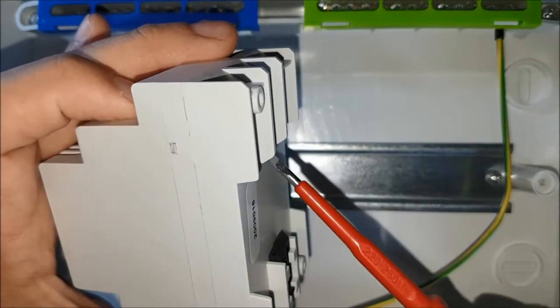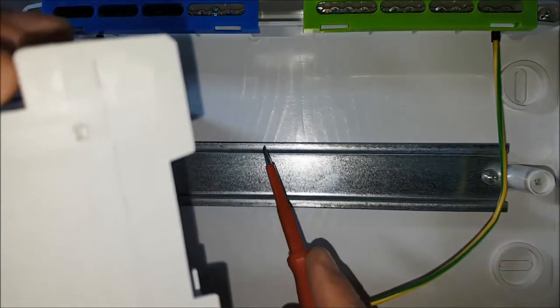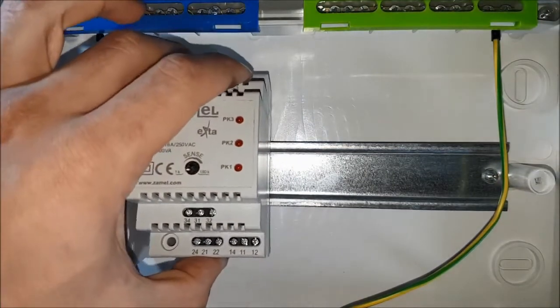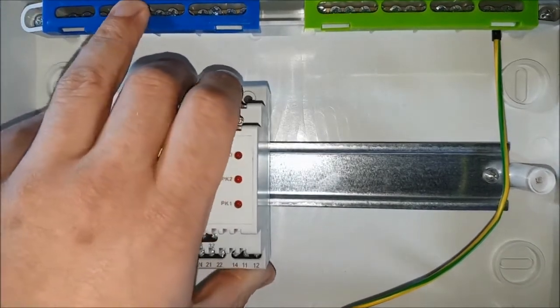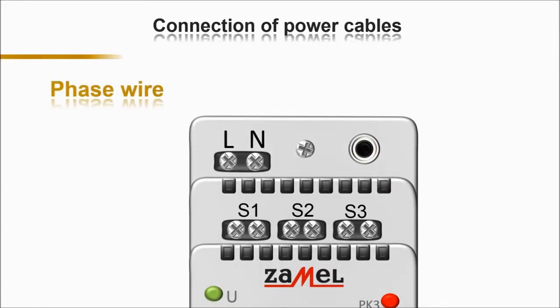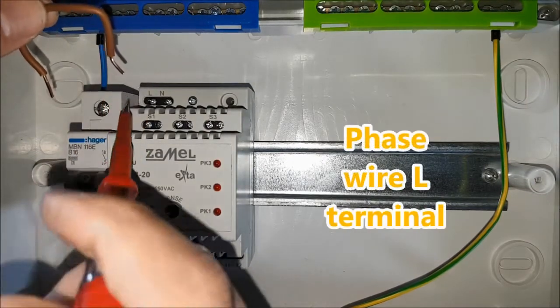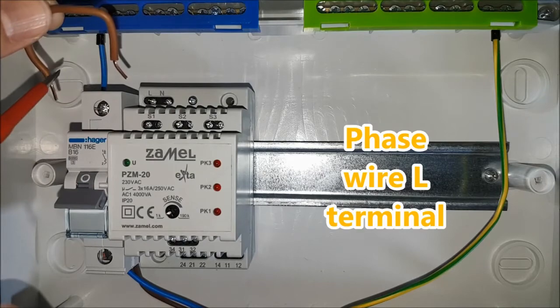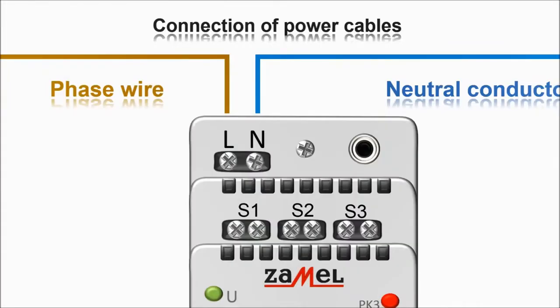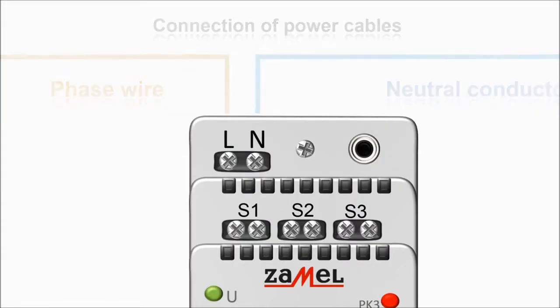Put the PZM-20 relay on the TH35 rail. Spring clips will be helpful. After installation, the device occupies 3 modules. Power cables connection. Connect the phase wire to the L terminal. Connect the neutral wire to the N terminal.